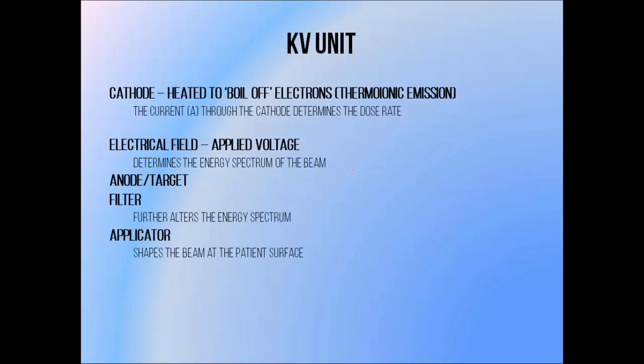Kilovoltage radiotherapy units are quite similar to diagnostic x-ray tubes. They both rely on a general design that's been in use for about 100 years. We're going to be talking about the beam generating components of a tube, not the power source. These are contained within a vacuum sealed container. The whole purpose of this thing is to generate a beam of electrons to slam into a target.